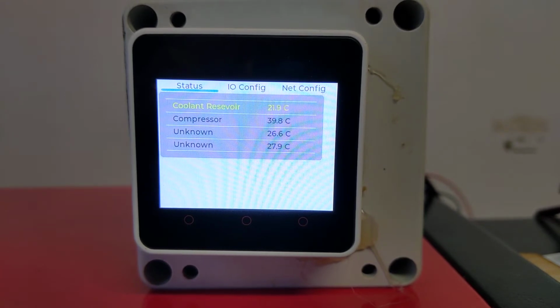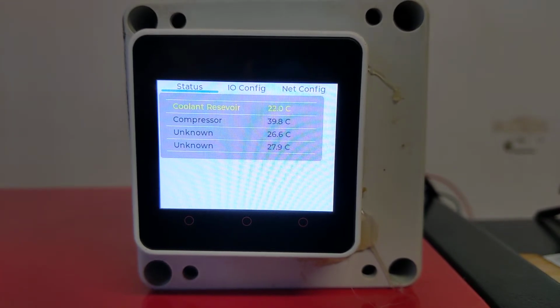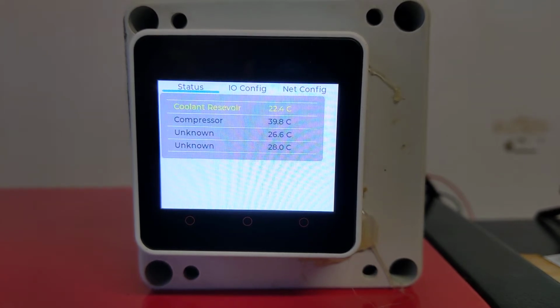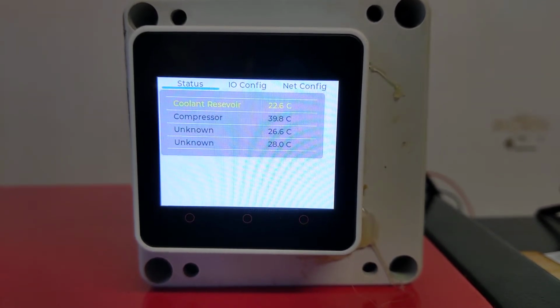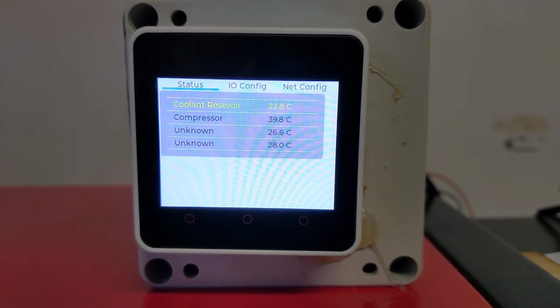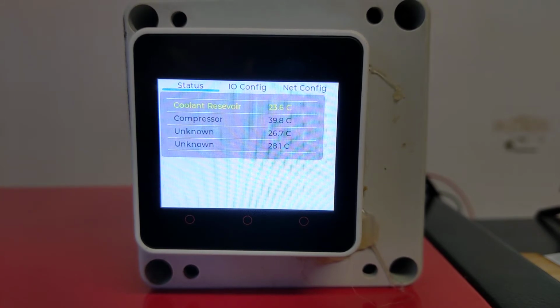Likewise, I've got a separate output set up for the compressor, so if the compressor temperature gets too high, then it will modify the signal to that to say, hey, back off a bit, let the compressor cool down. And then likewise, if the coolant gets down to 1 degree, like it's getting close to freezing, because I'm just running with distilled water right now, not antifreeze, then it will likewise back the compressor off.